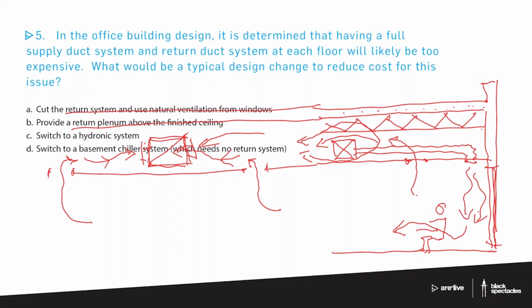The fact that I can place this return system much deeper into the space and still get all of this air to flow all the way over to it means I can have a much smaller return system compared to the supply system. So this whole space with all the lights, ductwork, and sprinkler pipes essentially becomes like a duct for that return system. It's not actually a duct, it's just the interstitial space below the slab above the ceiling, but it works like a duct, allowing the air to find its way over. In this context, from an air-based standpoint, that interstitial space is a plenum.